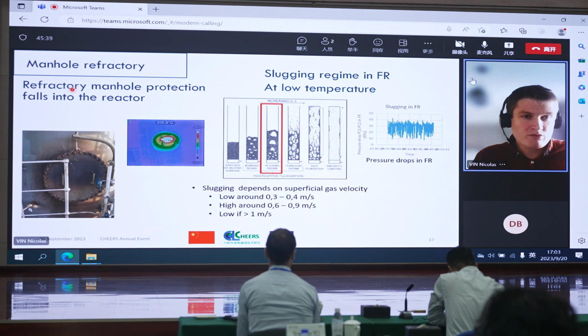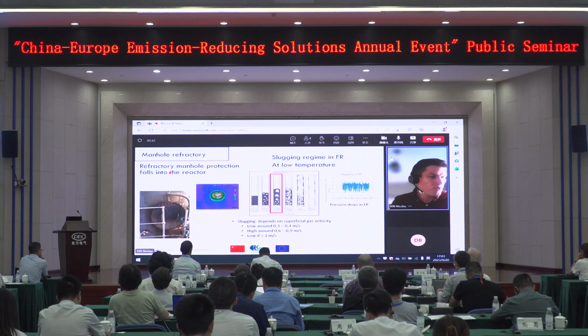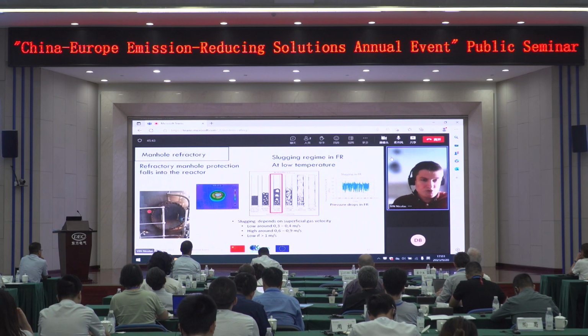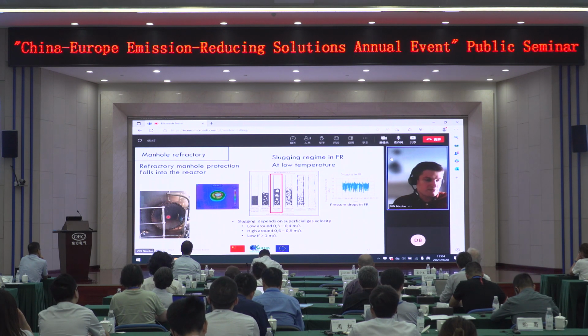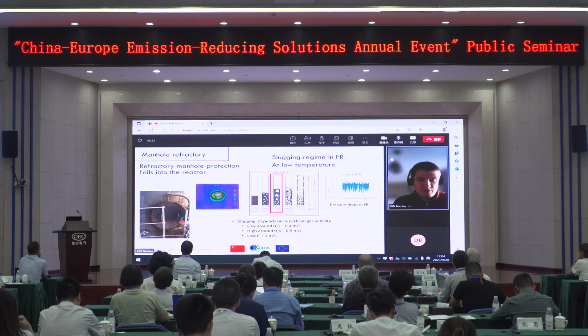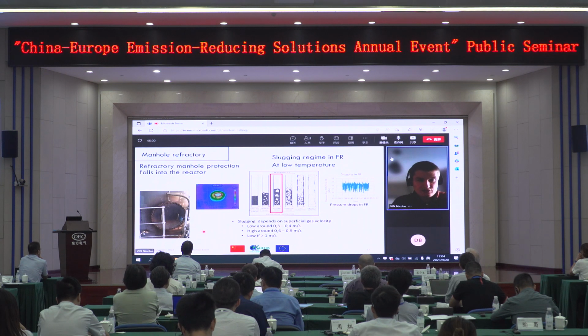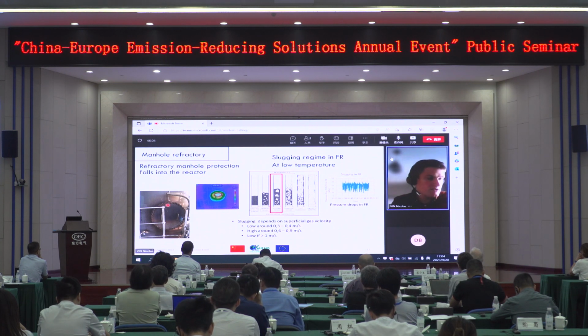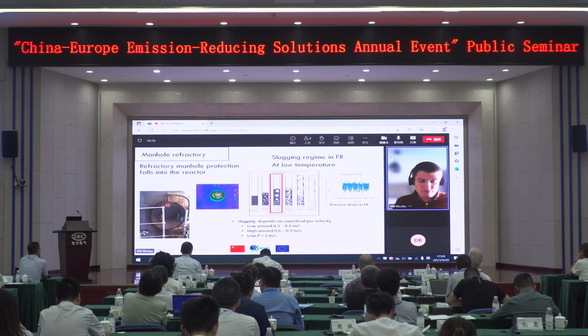One of them was some issues with the manhole refractory of the fuel reactor. You can see here a picture of the shell of the manhole, which was quite dark, meaning the protection of the refractory just behind was not there. In fact, the refractory fell down into the reactor, which is something we didn't expect. As you can see here, the temperature of the shell was quite important. So the question is how these pieces of refractory fell down into the reactor.